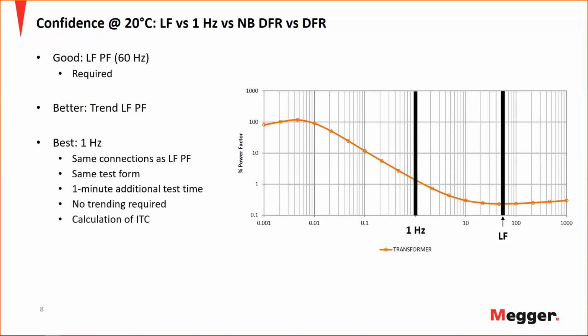In addition, what we can have now is calculation of what is called the ITC, or the individual temperature correction factor. This is the only way that an asset can be corrected back to 20 degrees C, and it pertains to only that particular asset. This ITC applies to line frequency, and it also applies to 1 Hertz. If you look in the standards, if you look anywhere else, there are no table correction factors for 1 Hertz, but the 1 Hertz must be corrected back to 20 degrees C in order for proper evaluation. And how can you do that? The only way is going to be ITC.